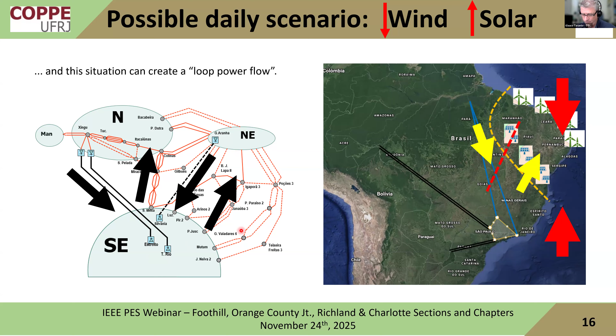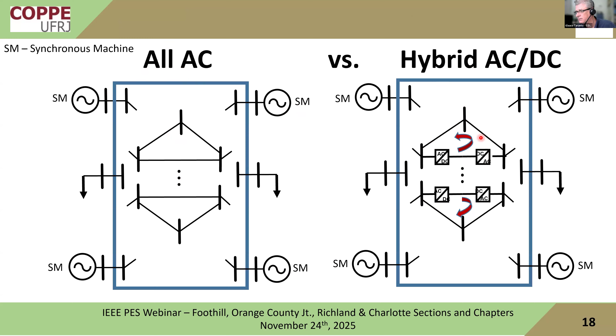Let me talk about how we can solve the loop flow problem created by this uneven curtailment combined with HVDCs embedded in the AC system. Historically, transmission was all AC and generation was essentially 100% synchronous machines, so there was no problem operating the system. But now networks are becoming hybrid, with HVDC links that can create these loop flows, and on top of that we're adding inverter-based generation — solar and wind — into the mix in Brazil.